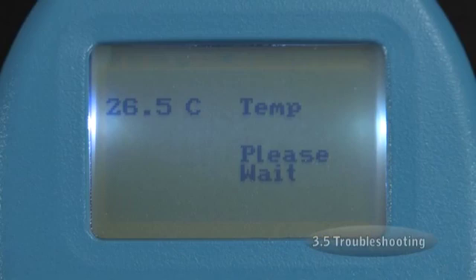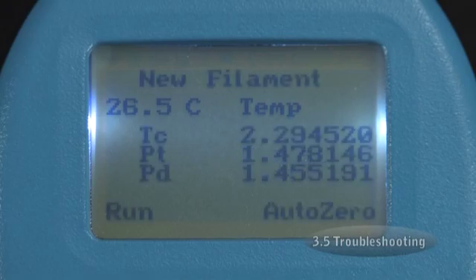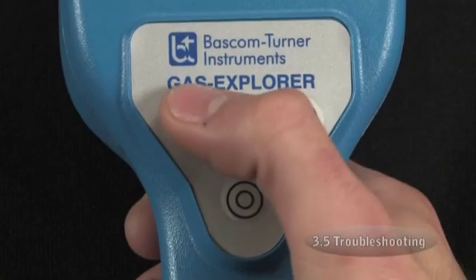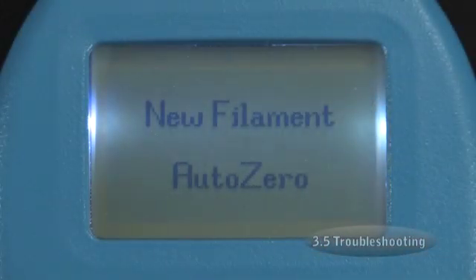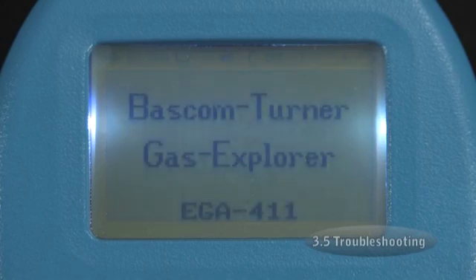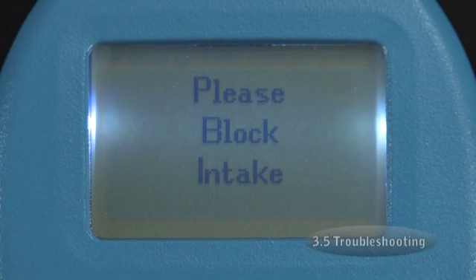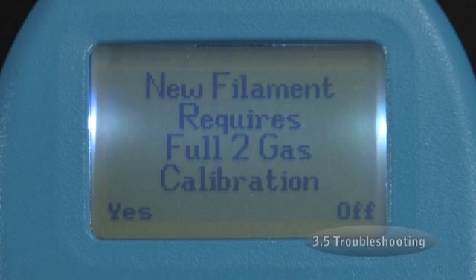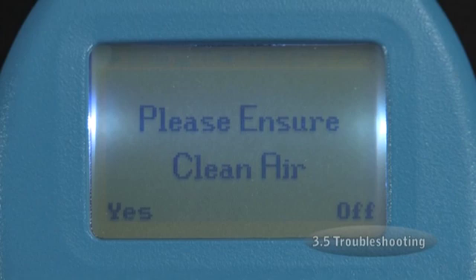A temperature will appear on the display for several seconds accompanied by the message, "Please wait." Shortly, the word Continue will appear in the bottom left corner. Press the left button. The Explorer will start running a new filament auto zero, and then it will restart with the typical startup procedure. When prompted on the display, block the Explorer's intake. The message New Filament requires full 2-gas calibration will appear for a second time on the Explorer display. Press the left button beneath the word Yes. The Explorer will ask you to please ensure clean air. Press the left button beneath the word Yes to proceed.